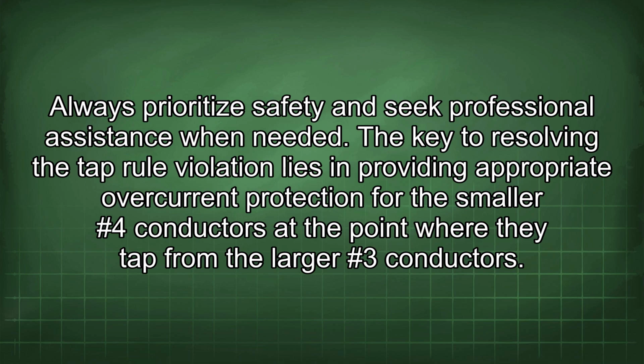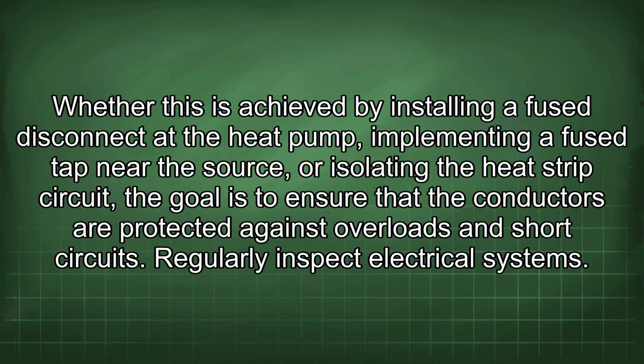The key to resolving the tap rule violation lies in providing appropriate overcurrent protection for the smaller #4 conductors at the point where they tap from the larger #3 conductors. Whether this is achieved by installing a fuse disconnect at the heat pump, implementing a fuse tap near the source, or isolating the heat strip circuit, the goal is to ensure that the conductors are protected against overloads and short circuits.